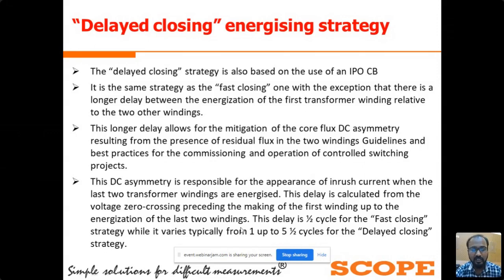So we are giving a 1.5 cycle delay between the R phase and the Y and B phase. At the time of commissioning only, we finalize how much delay we can give between the R and the Y and B pole. During commissioning, by observing the waveform, we finalize all these settings.